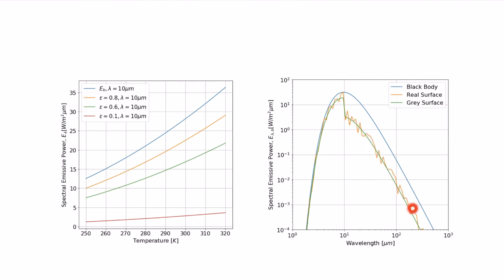If we pick a single wavelength, the emissivity value is going to very much change what we're going to read if we measure the emission at a given wavelength. Here's the black body. If I had an emissivity of 0.8, I would get this line. If I had an emissivity of 0.6, I would get this line. That's why in your thermal camera, you have to set the emissivity of the surface. Let's imagine the sensor on the camera is reading an emissive power of 12.5 watts per meter squared micron at 10 micrometers wavelength. If I had a black body with an emissivity of 1, my camera would tell me I was reading a temperature of 250 Kelvin.